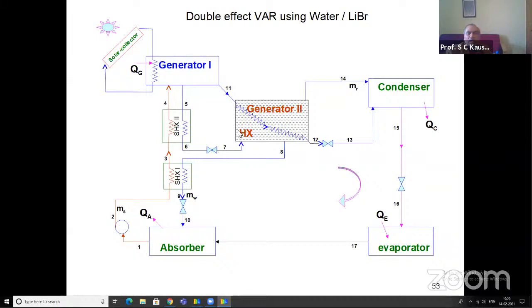Now you can see that just by providing this one intermediate heat exchanger between the generator and the condenser of the system, the cooling produced in the evaporator is nearly twice. Why? Because first stage refrigerant vapor generation is this one, and second stage refrigerant vapor generation is this one. So the amount of refrigerant vapor condensed in the condenser is nearly twice as compared to the single stage system. So the cooling capacity provided in the evaporator is also nearly twice. With the same heat input, we are able to increase the refrigerant vapor generation as well as the cooling effect in the evaporator nearly twice. So the COP is also nearly twice in the case of the double effect generation water lithium bromide system.